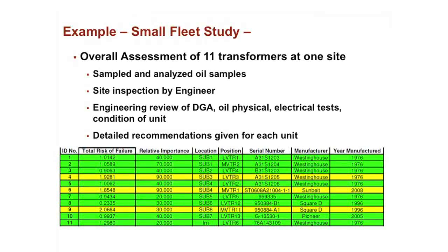But in this case, a design study was done on basically every design, and because it was a smaller number of transformers and the value of the assets was high, a very detailed study was done on every particular transformer here. But that's not always the case. You can have a much larger fleet, and then you would maybe just focus on 10% of the transformers in a very detailed way, and then less detailed for a larger number of the transformers.